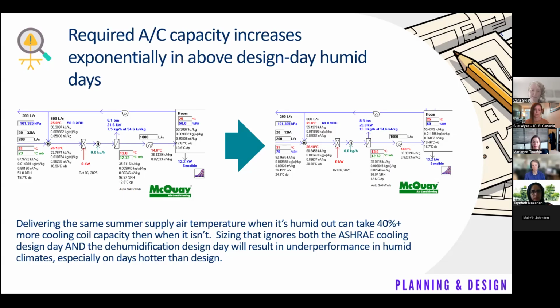And so on a day that I presented at 500 McNabb, which is this building that has some overheating issues that we worked on together, I was presenting about the building. It was 34 degrees Celsius, and the air conditioning load was 140% of my design day, which was 31 degrees Celsius, 50% humidity. So the engineering metric that I use gets substantially overshot when we see increases in temperature in humid environments. And so that means that when we are sizing our coils, we really have to be mindful of what future conditions we're trying to accommodate and how we oversize.